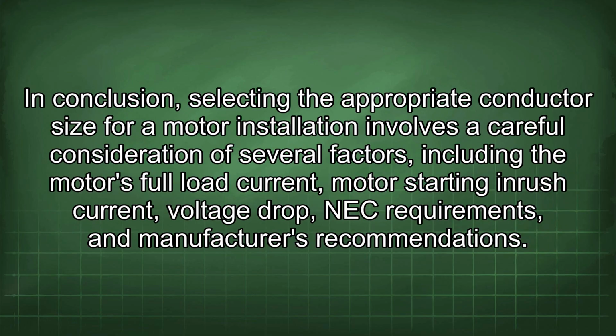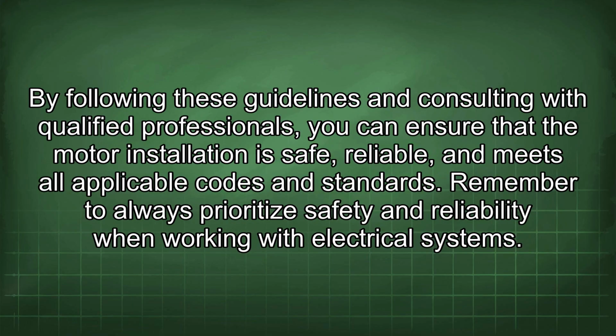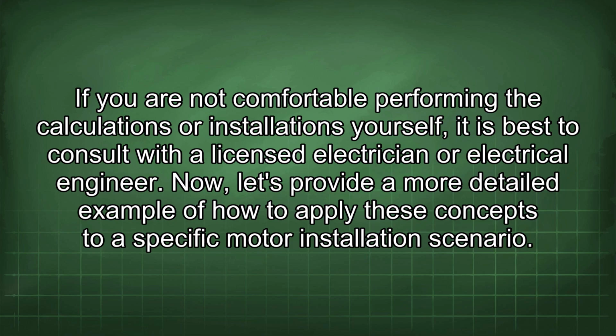In conclusion, selecting the appropriate conductor size for motor installation involves a careful consideration of several factors, including the motor's full load current, motor starting inrush current, voltage drop, NEC requirements, and manufacturer's recommendations. By following these guidelines and consulting with qualified professionals, you can ensure that the motor installation is safe, reliable, and meets all applicable codes and standards. Remember to always prioritize safety and reliability when working with electrical systems. If you are not comfortable performing the calculations or installations yourself, it is best to consult with a licensed electrician or electrical engineer.